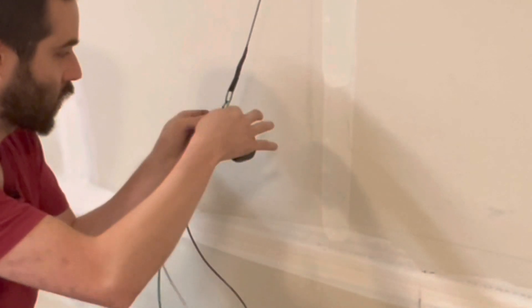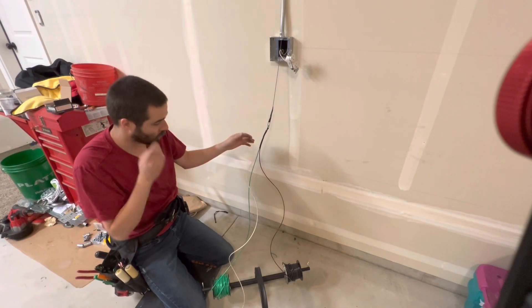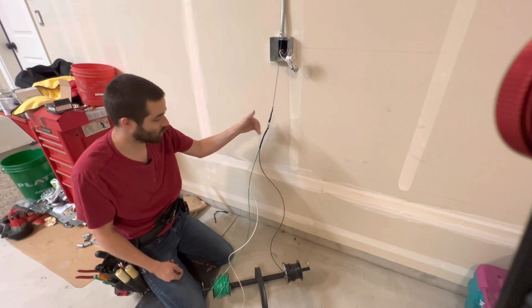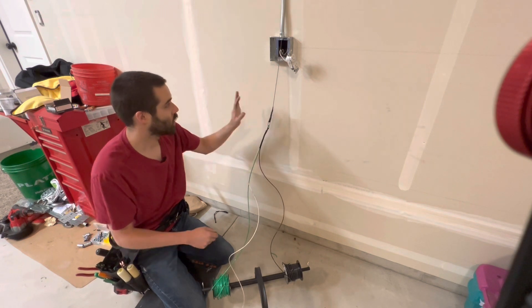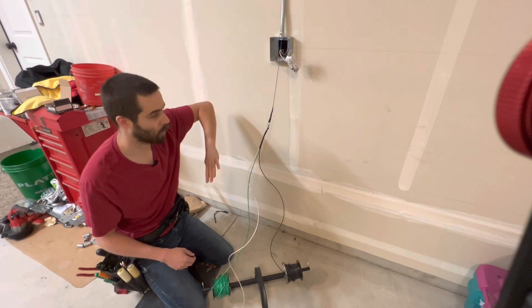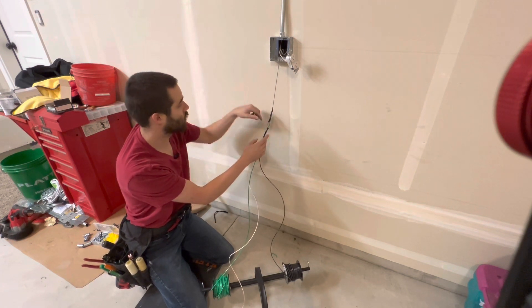This is just a basic wire head — nothing too extreme. There are other methods I can show you later, which involves stripping out the ends of the wire to make a stronger head for pulling so none of the other wires fall off. But we're just going a short distance and we won't have any problems with these two wires taped to the pulling wire. Thanks to the wire caddy, I don't have to have anyone else helping me with the wire pull — this will spool off by itself.